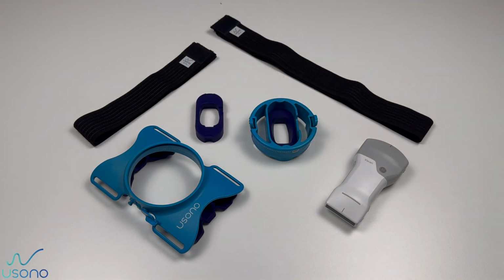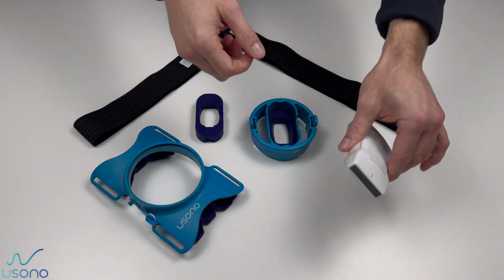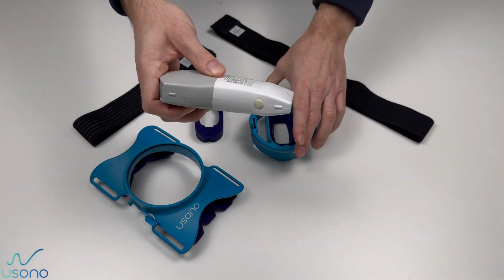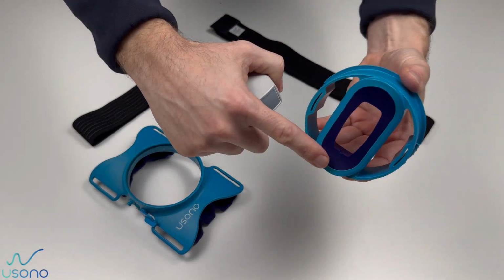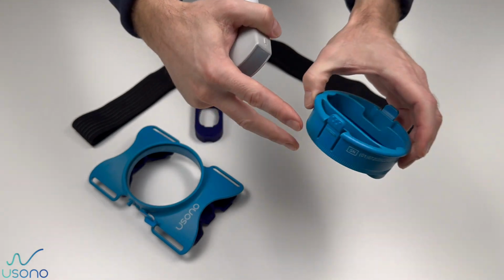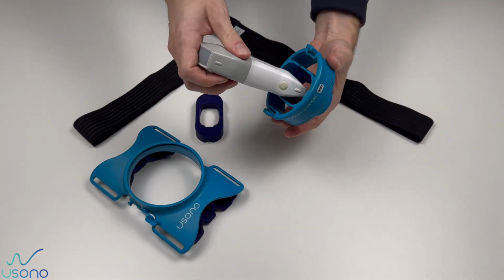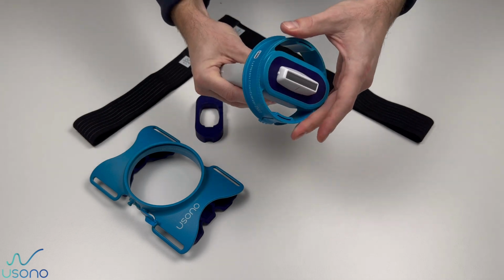Now you can put the probe into the adapter from the top. Make sure to align the marker of the probe with the matching notch from the bottom silicone ring. Please note that this will be different for each specific ultrasound brand. When viewed from below, it should be 100% fit.